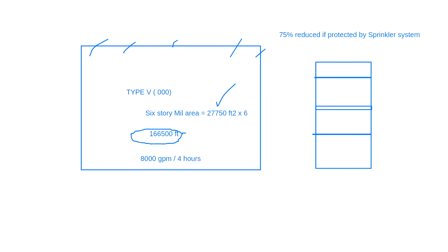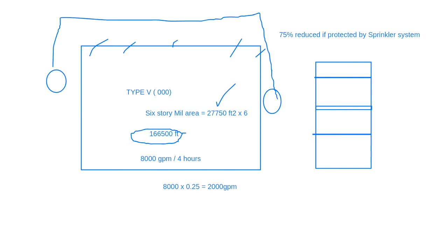We discussed in Fire Protection 1 the rating of the hydrant, right? So the rating starts from 1,500 GPM for Class AA hydrants, and our requirement here is 2,000 GPM. So for this application, we need a minimum of 2 fire hydrants, right? And the maximum distance between the hydrants should not be more than 500 feet or 152 meters. So this is how we have to calculate the fire flow requirement for those buildings.